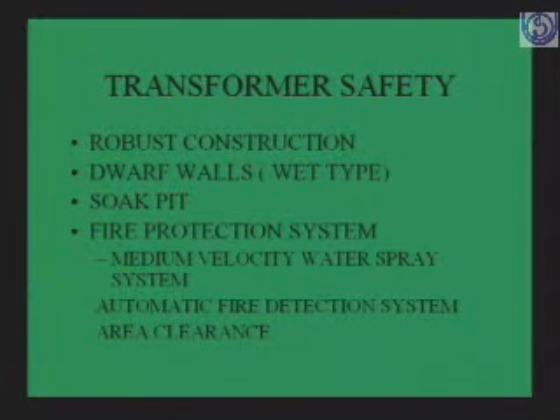Then there are good fire protection systems. For transformers, medium velocity water spray systems are the best. Placed around the transformer at a distance of 2 or 3 feet, upon actuation it throws water at very high speed over the transformer, mixing with the oil. Emulsification happens and it extinguishes the fire.